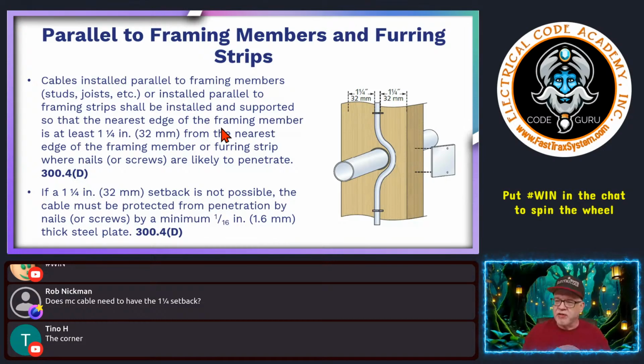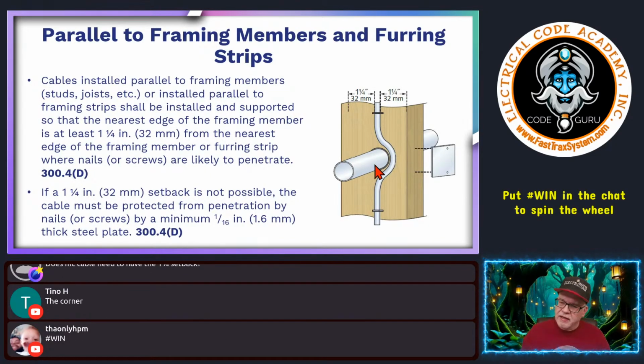So in this case, obviously they were okay. And then somebody came along, a plumber, and moved your cable out of the way. We'll say the electrician didn't do this, right? And ran it through this bored hole right here. And now you run the risk, you don't have the 1 1/4 right here. And it could apply to either side. If that's the case, then you're going to need a nail plate because they could penetrate.